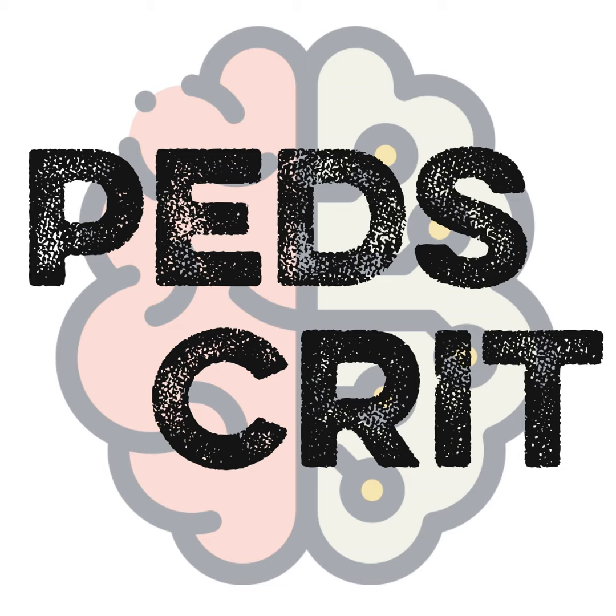Oh, excellent. Now, how does the ventilator know when the patient wants a breath in most cases? And then what are the different ways that this can go wrong? Big question. So we'll start off with how the ventilator knows. So there are different types of triggers. The ventilator is a machine. It's looking for a specific signal that says, oh, it's time for me to give a breath. The obvious one is time. If you have a patient who's paralyzed, they're not making any effort at all, or for whatever reason they're not making a respiratory effort, eventually the respiratory rate that we set will kick in. The ventilator will say, too many seconds have gone by. I need to give a breath. So that's our time trigger.